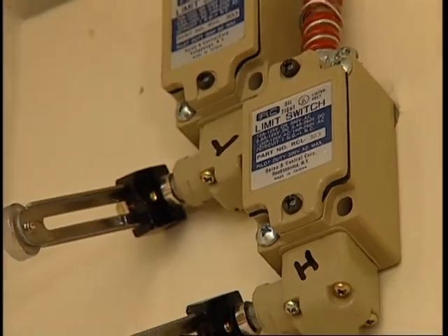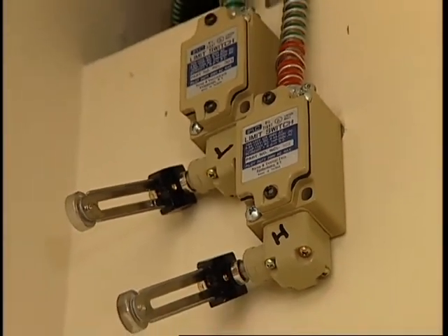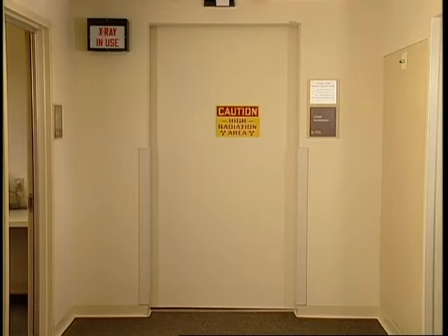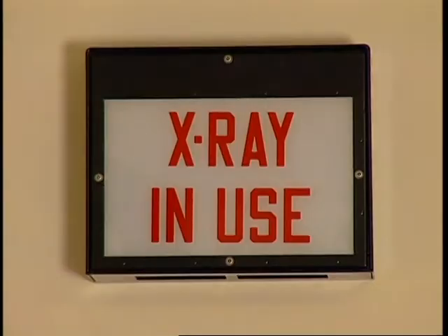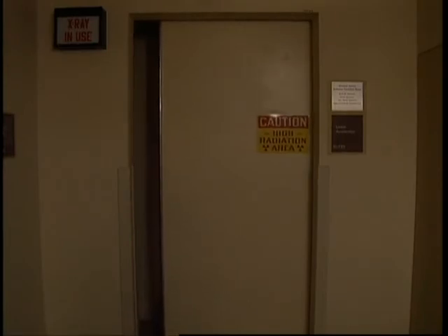Door interlock switches are mounted to the door support system. The interlocks ensure that room doors are closed during linac operation. Should a facility experience a power loss and there is no ancillary power available, battery backup power is provided to open the door. The door will automatically open if the power is interrupted. Door opening speed during battery use is significantly slower.